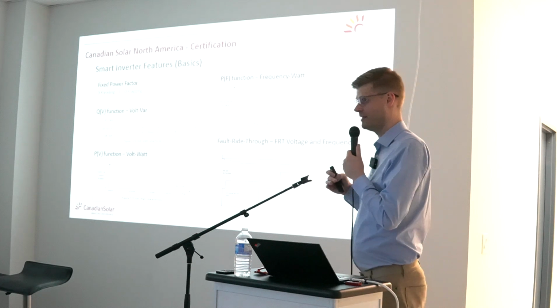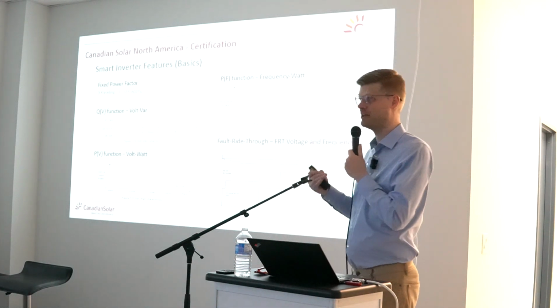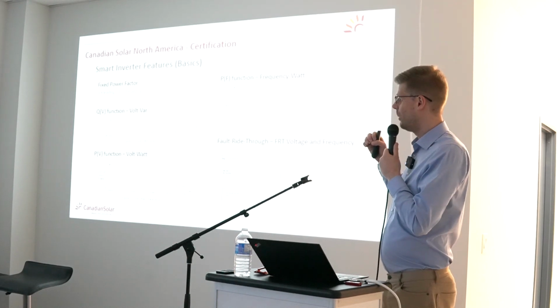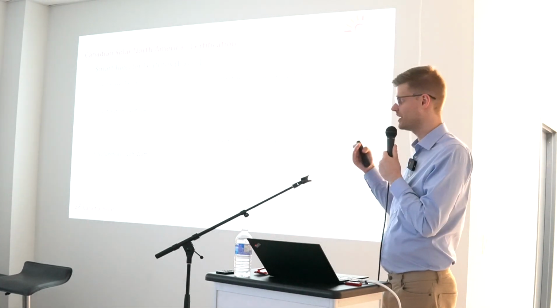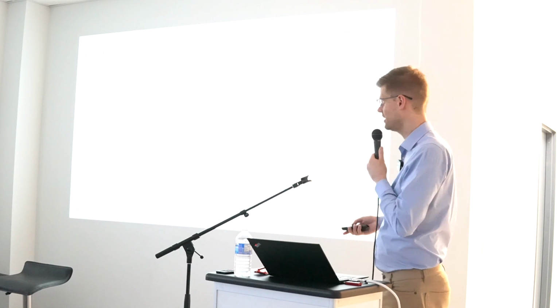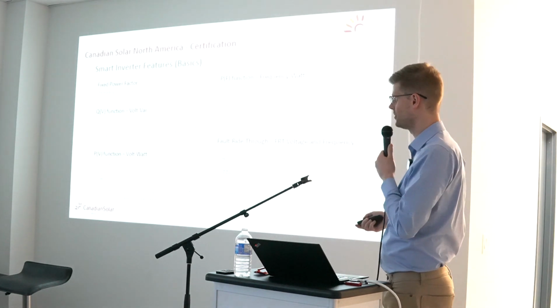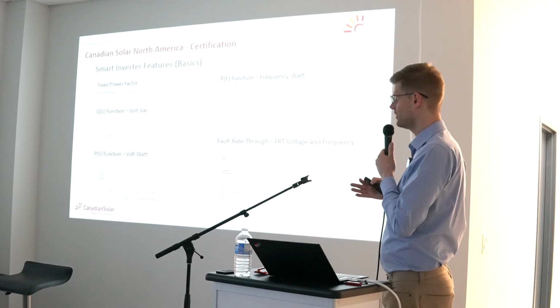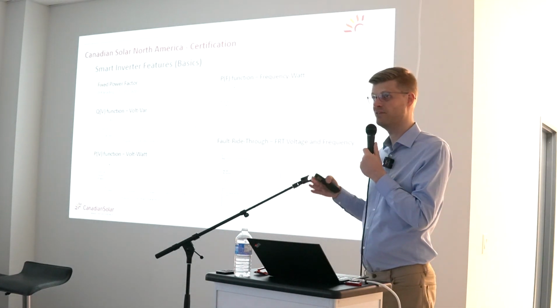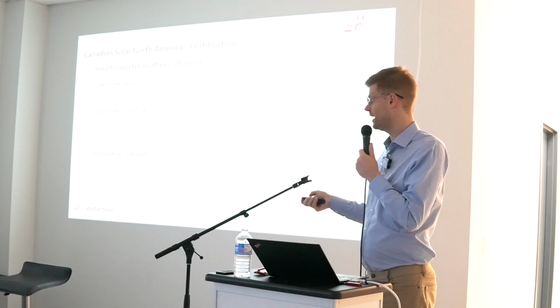Quick jump into smart inverter features. Some of them are already implemented within the older current grid code, but as I mentioned, a lot more of the utility companies are asking for features where the distributed generation is participating in grid stability and fault recovery. Some of those functions, and I don't want to go into it too deeply, are a Q of V function, where you have additional reactive power based on voltage. We have a P of V function that ramps down the output power if the grid has an overvoltage condition. That's something Hydro One is also requesting for some of the projects.